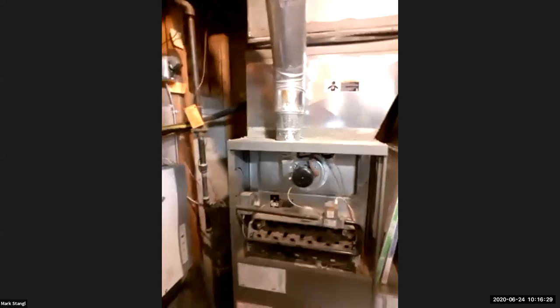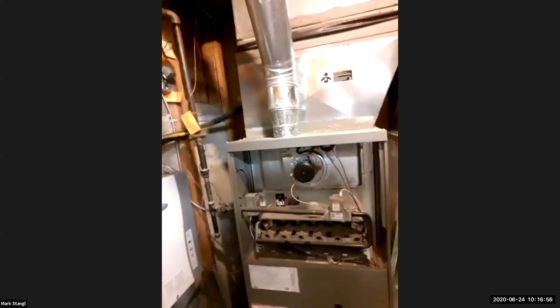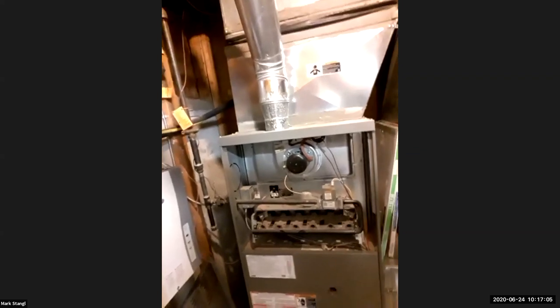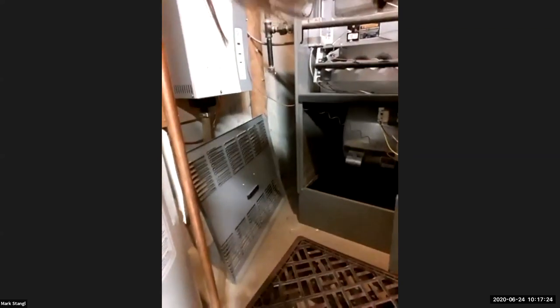This is my simpler system — it's an 80% efficient forced air gas furnace, originally installed when I purchased this house six years ago. It has some common elements to Charles's system and we've added a few other things. We have an inducer fan that comes on, and unlike Charles's system we have a conventional chimney that goes from single vent to B-vent all the way up to the roof through another story. We always check our furnace vents very carefully — we look for rust and leakage and often find them deteriorated and needing replacement in older homes.